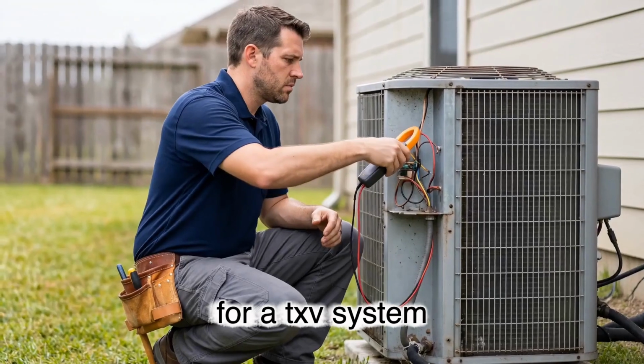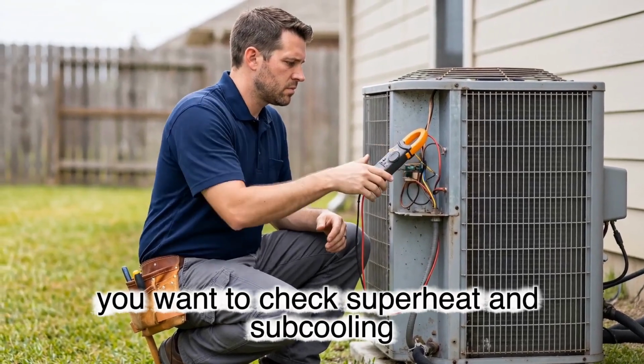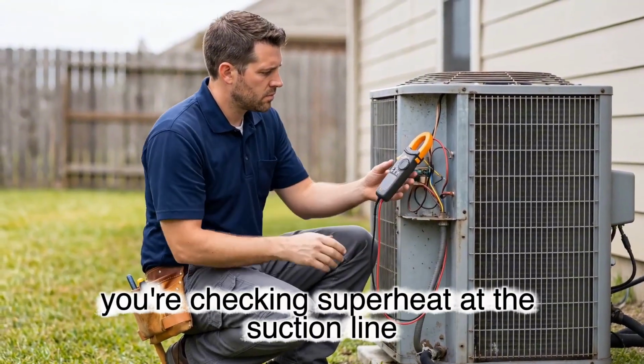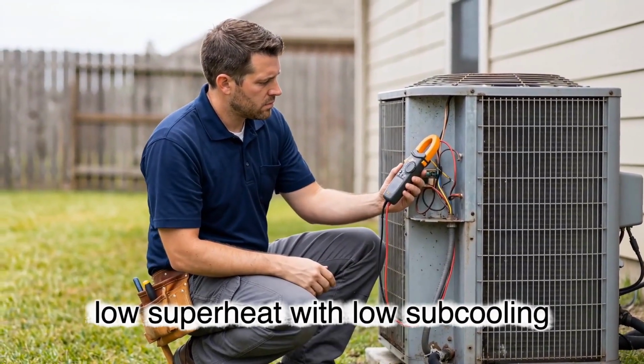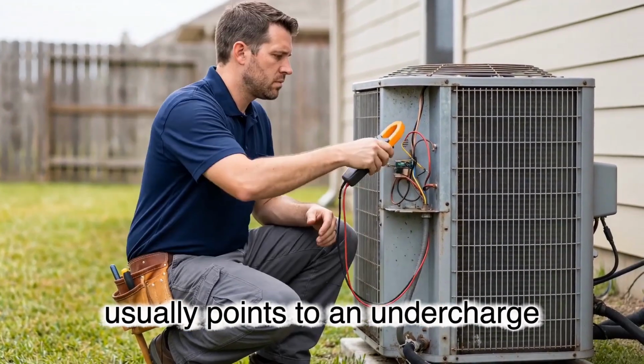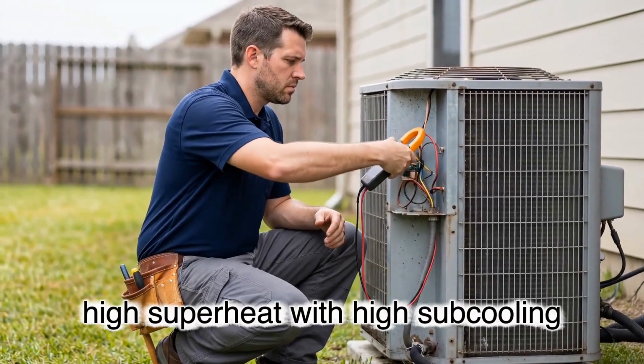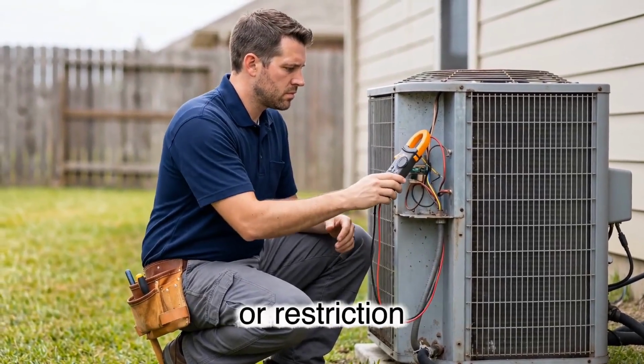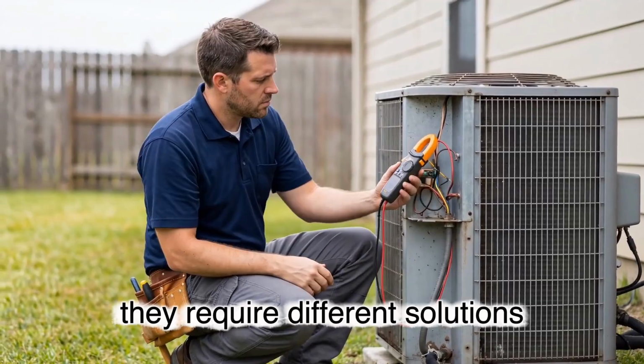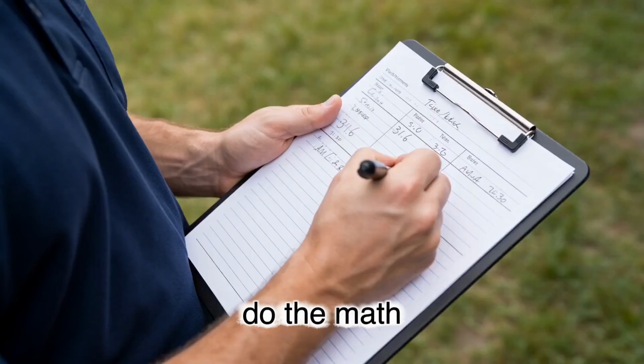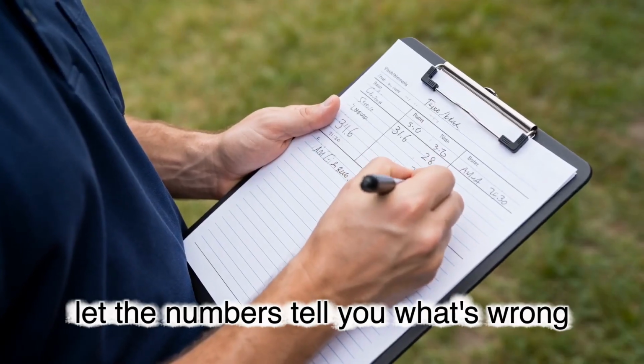For a TXV system, you want to check superheat and subcooling. For a fixed orifice system, you're checking superheat at the suction line. Low superheat with low subcooling usually points to an undercharge. High superheat with high subcooling often points to a metering device issue or restriction. These are different problems. They require different solutions. Take the measurements, do the math, let the numbers tell you what's wrong, not your gut.